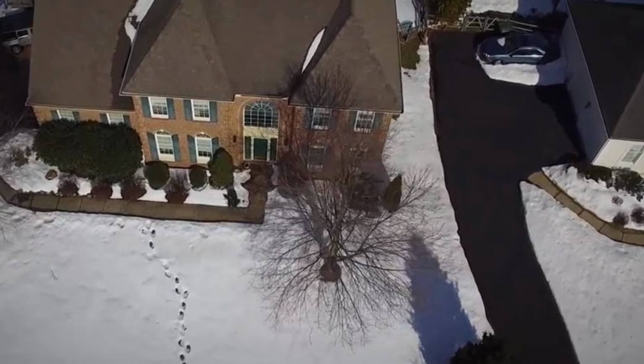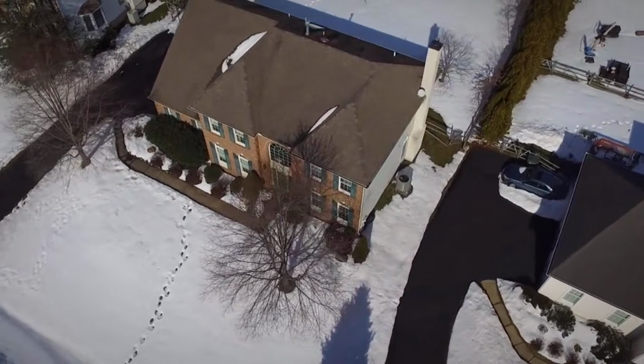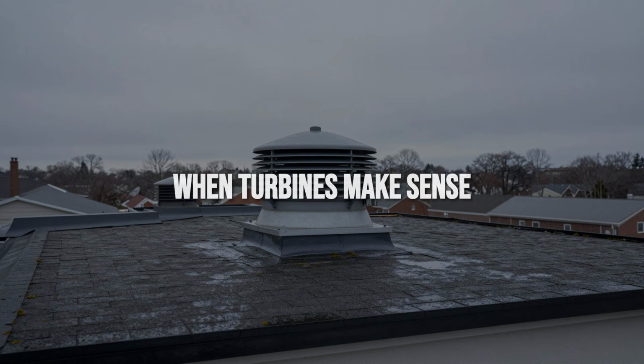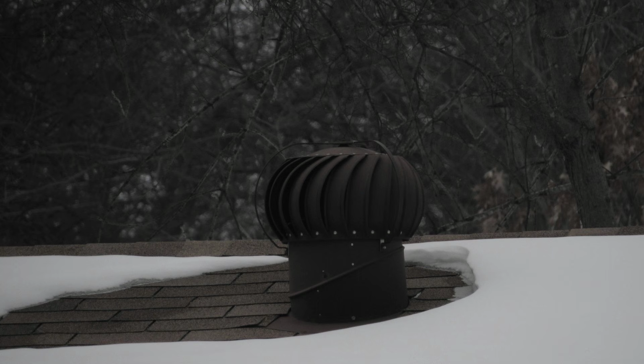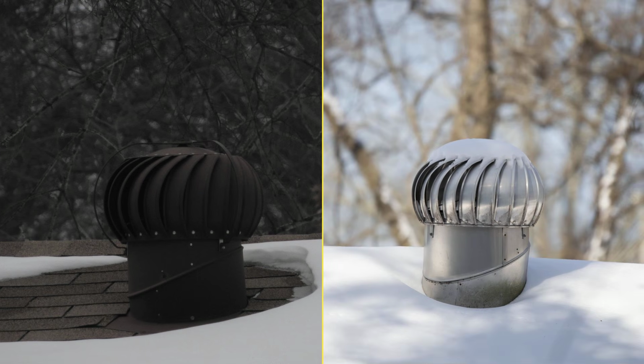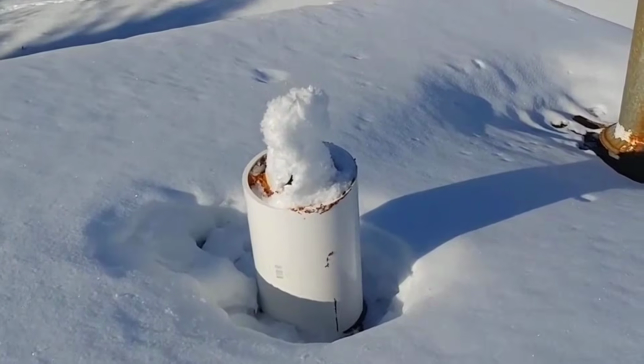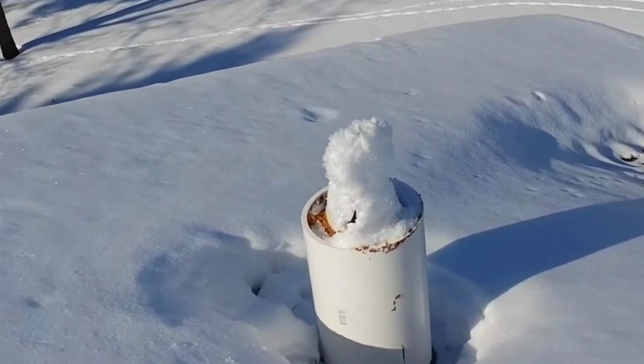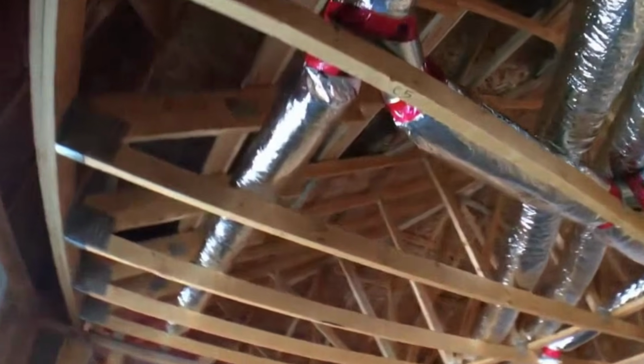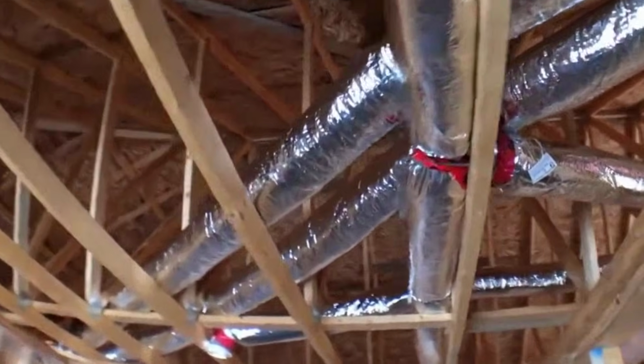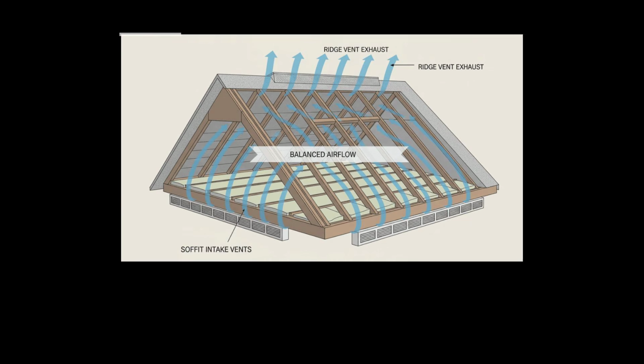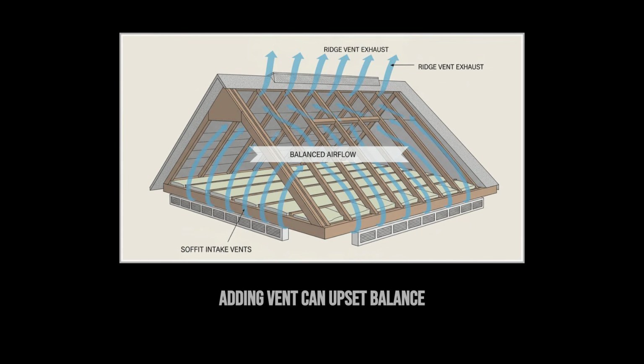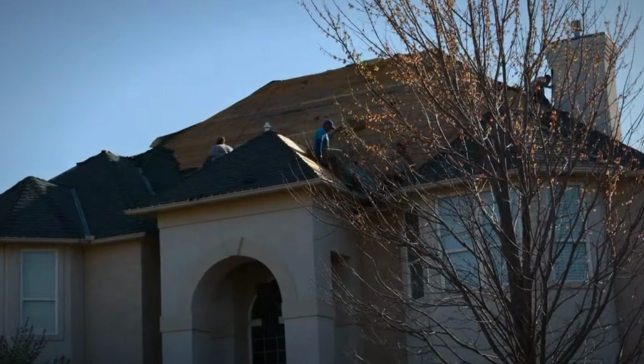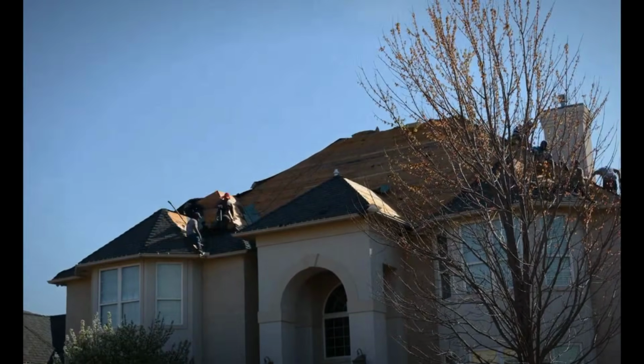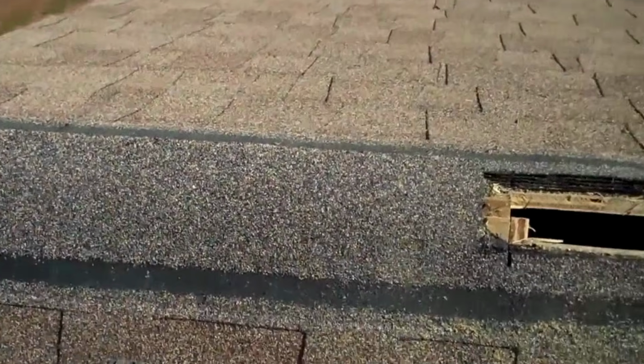But in cold climates, or in homes with modern high-performance building envelopes, a turbine is likely not the right fit. In winter, interior moisture can freeze the vanes solid, shutting the system down precisely when consistent performance matters most. In an airtight home, where mechanical ventilation is already managing air exchange, introducing a passive exhaust point can disturb the pressure balance the system was engineered to maintain. For most homeowners, particularly those building new or re-roofing, a ridge vent is probably the more practical path.